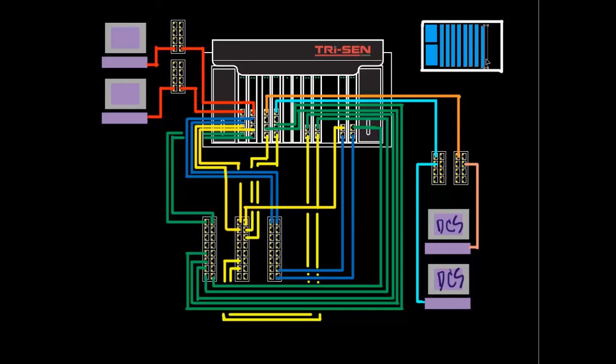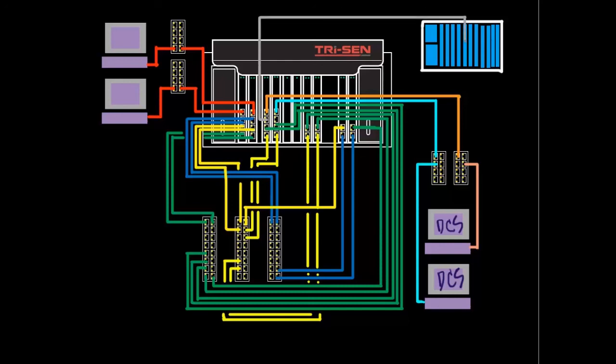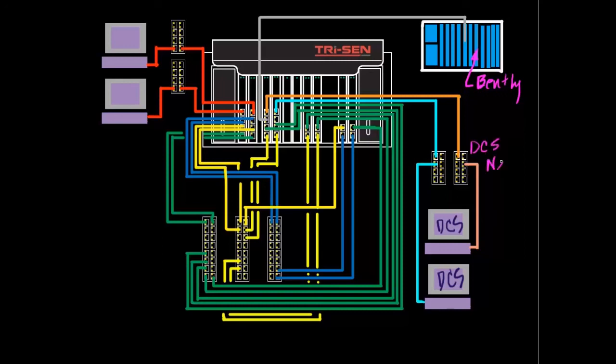They're available with either serial or TCP IP or TCP IP Modbus. So the second port on each of those TCP IP boards would be configured as host or master networks for the Modbus systems. Since we only have a simplex Bently we're going to just put in one network, no switch. Once again it probably makes more sense to add a switch in as well. Then if the customer wants to connect some other devices in they can.